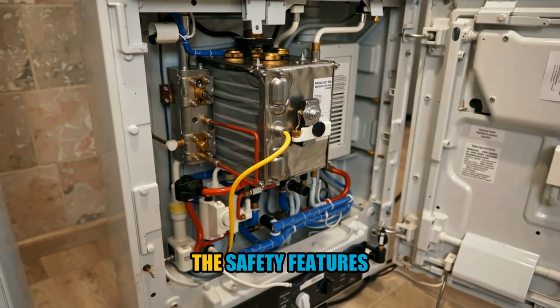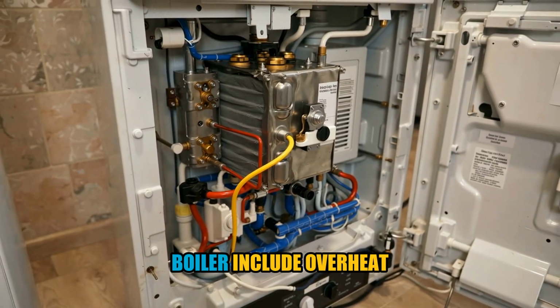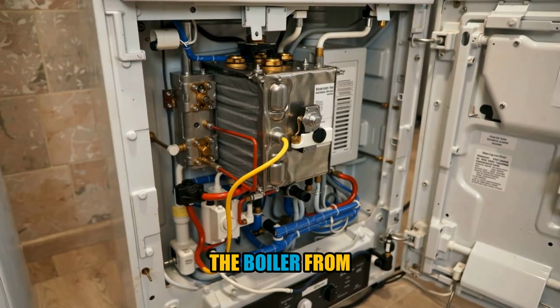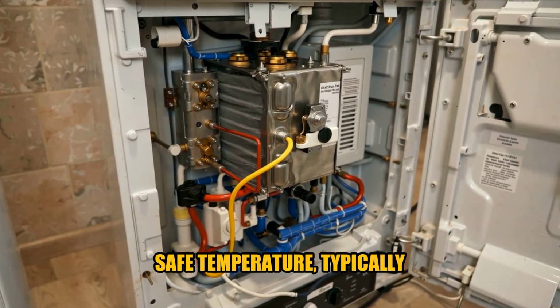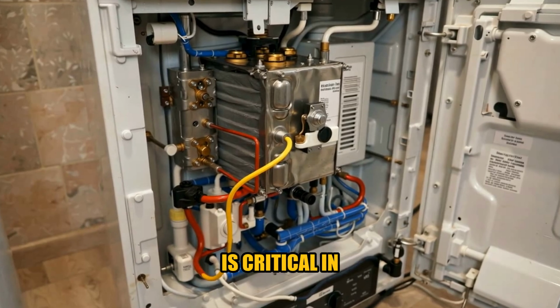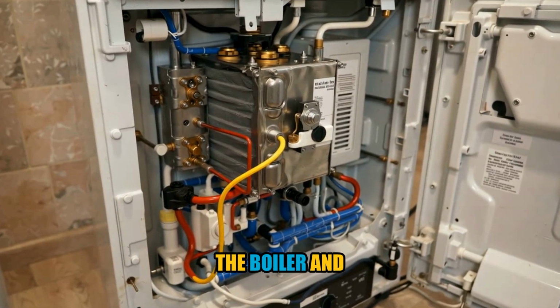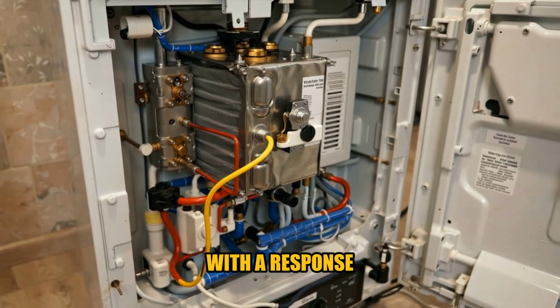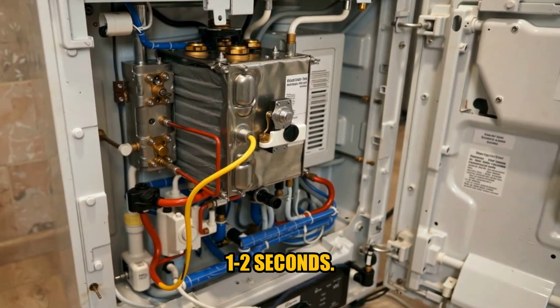The safety features of a condensing boiler include overheat protection, which prevents the boiler from operating above a safe temperature, typically 110 C. This feature is critical in preventing damage to the boiler and ensuring safe operation, with a response time of around 1 to 2 seconds.